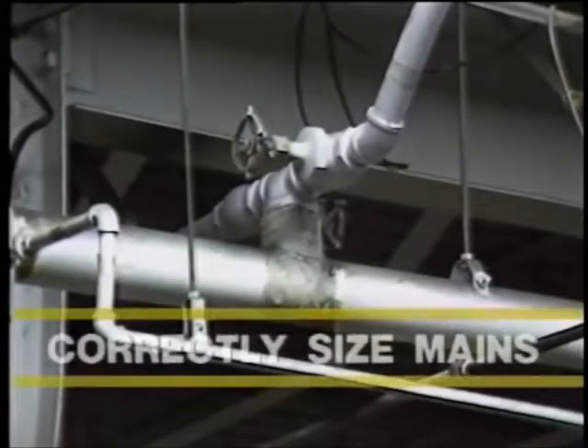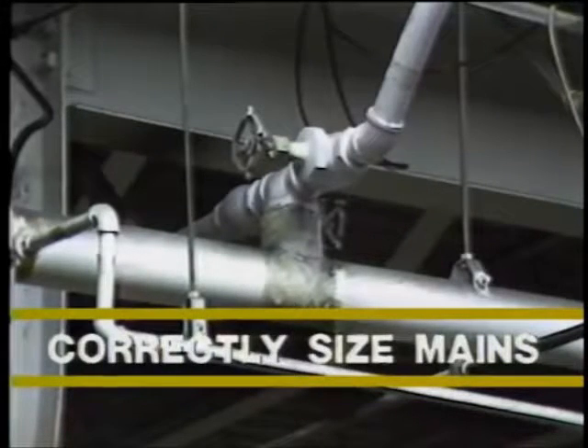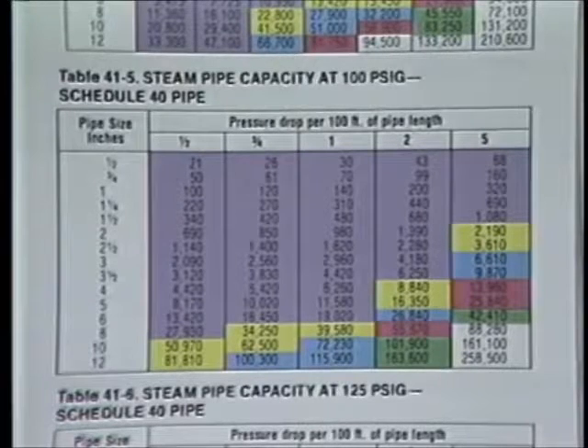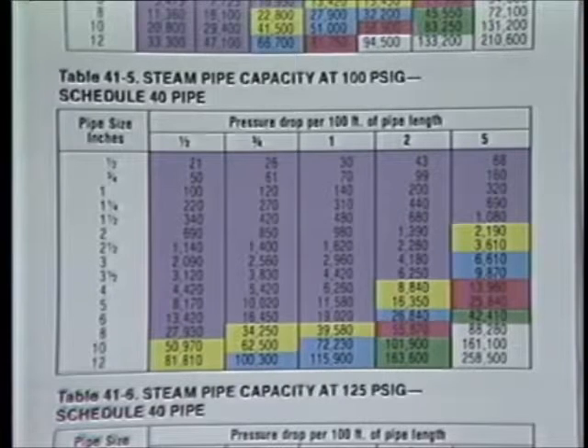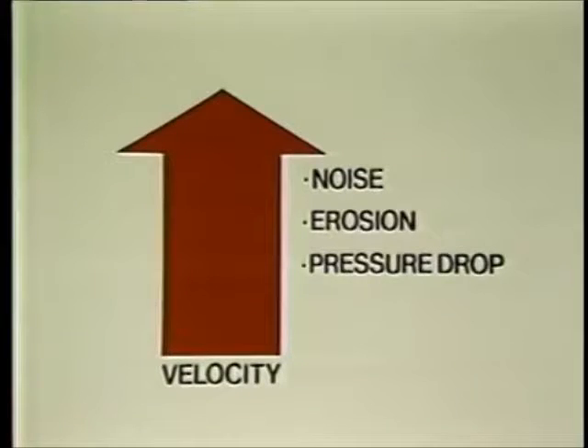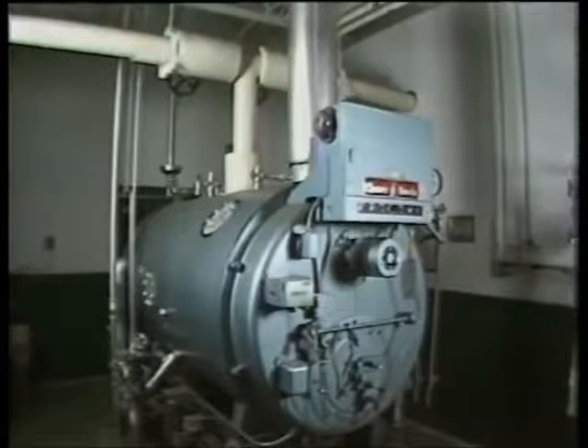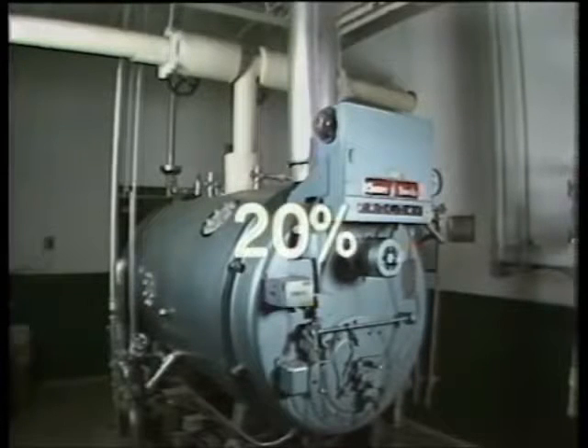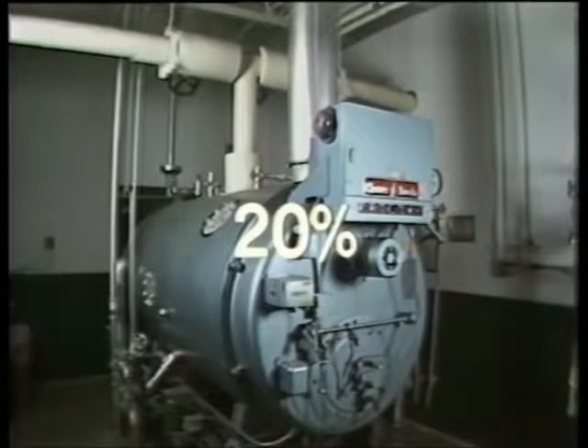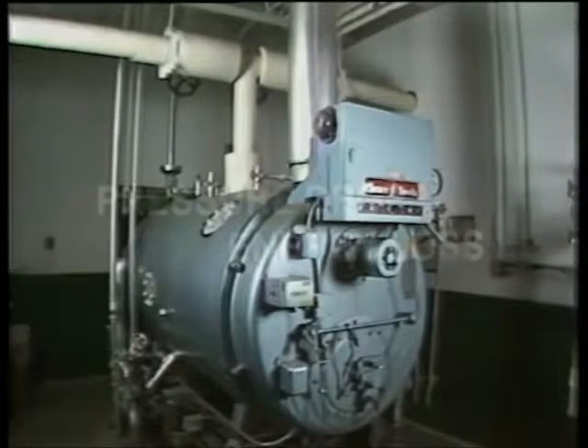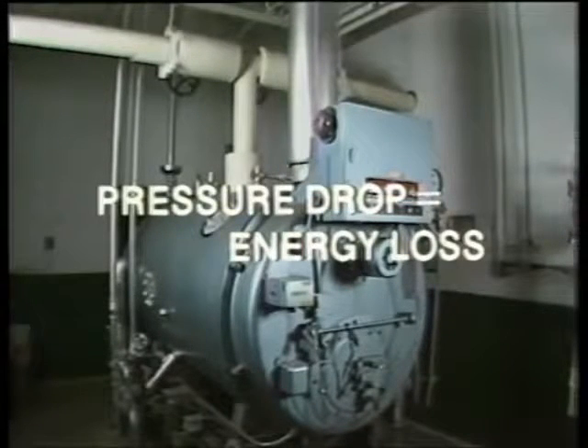Steam mains must be correctly sized to ensure efficient operation and to minimize maintenance costs. The size of the steam main piping is determined by the allowable pressure drop and velocity for a specific pressure. As velocity increases, so do noise levels, erosion potential, and the amount of pressure drop. The greatest pressure drop in the distribution system should not exceed 20% of the maximum boiler pressure, radiation and friction losses included. Remember, pressure drop is energy loss.